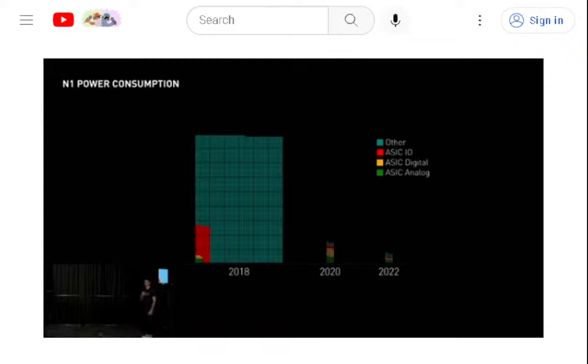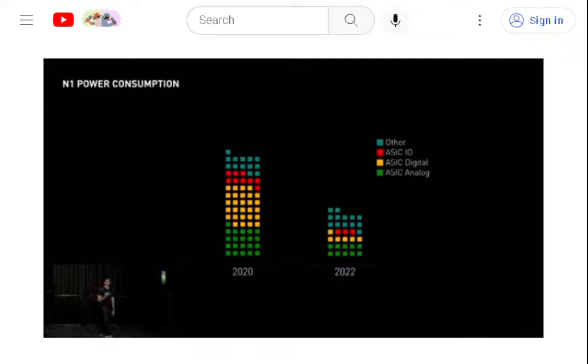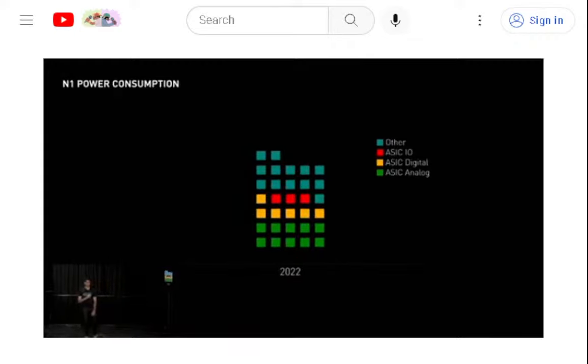Back in 2018, we were sending every sample from every channel off the device for processing, which burned a ton of power. In 2020, we brought spike detection onto the chip. As you may know, neurons transmit information by firing. So simply monitoring for these spikes and only sending these spike events off the implant acts as a very efficient form of compression. And over the past 2 years, we've continued to make optimizations within the ASIC, dropping the total system power consumption down to just 32 milliwatts and doubling battery life. Let's take a look at our on-chip spike detection algorithm, which makes our battery-powered implants possible.